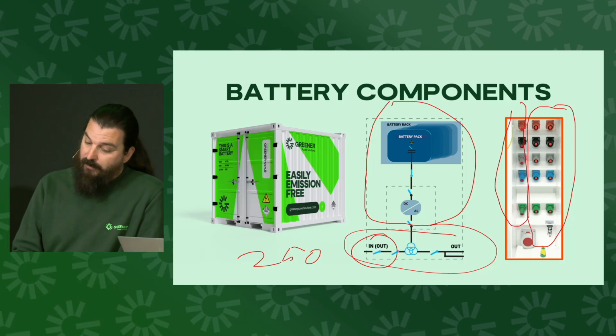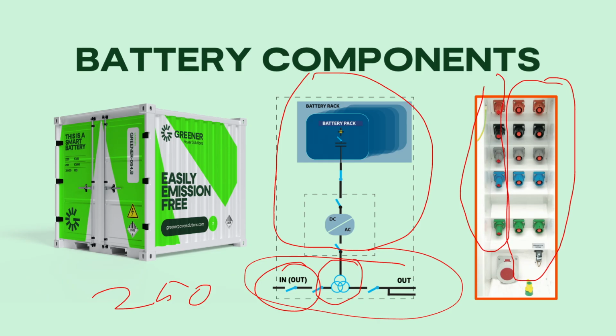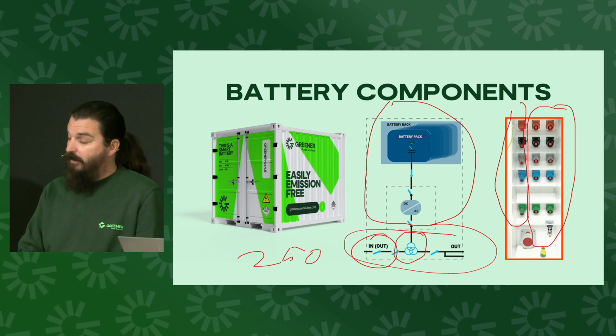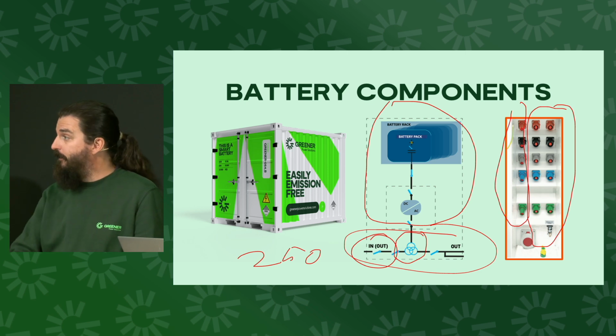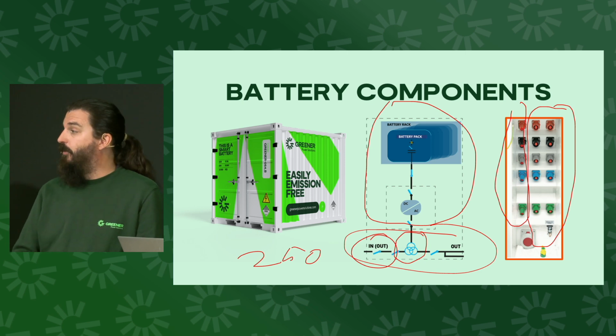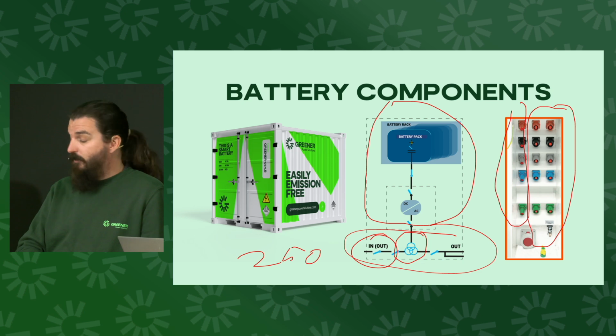less energy available. One of the other key factors that we have in our battery systems is this transformer in the middle, which has 3 legs, 1 leg connecting to the input, a leg connecting to the inverter, and a leg connecting to the output. The 2 legs connected respectively to the input and the inverter are 315 kVA, and the output is obviously double that at nearly 650 kVA, slightly over, just to handle a bit more peak power. Yep. So we can stack the inverter power on top of the input, as you just mentioned, but we can also parallel the batteries together.